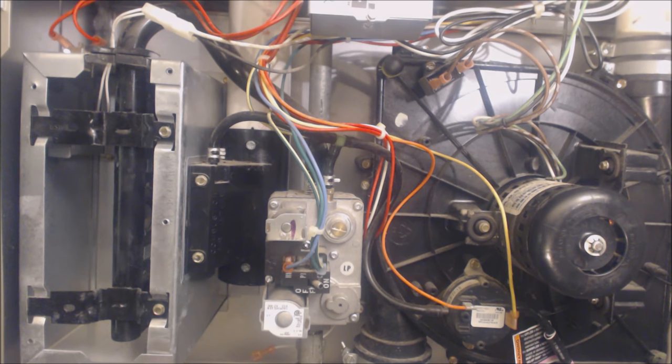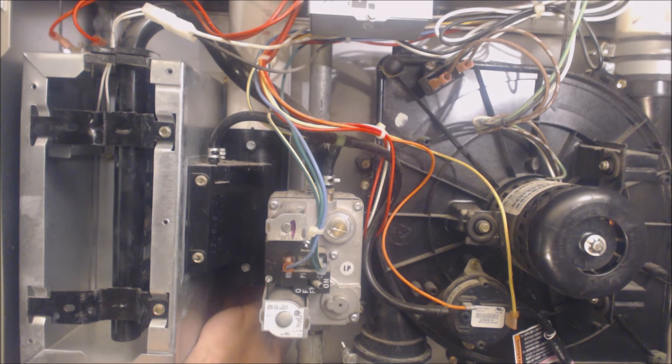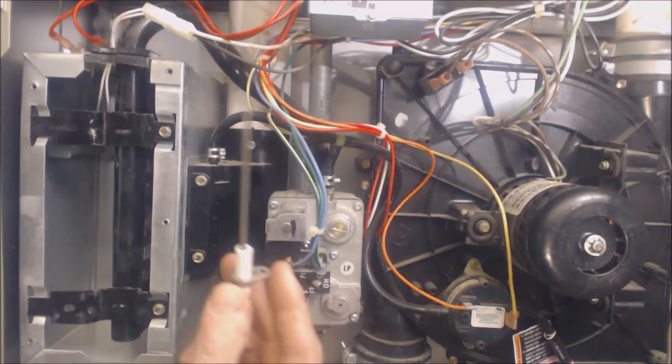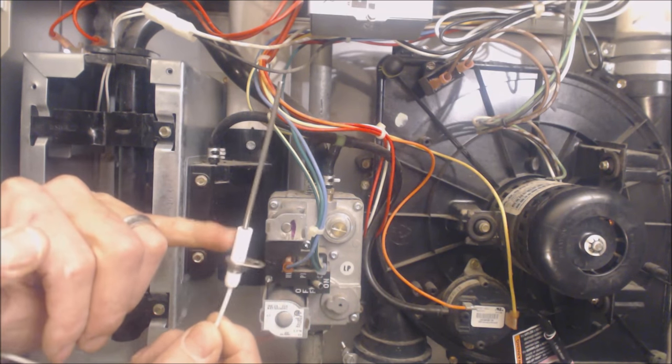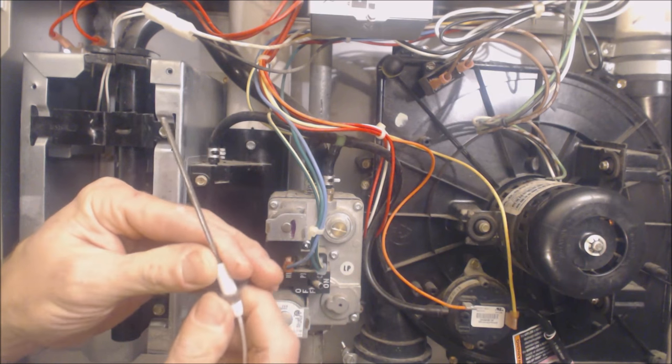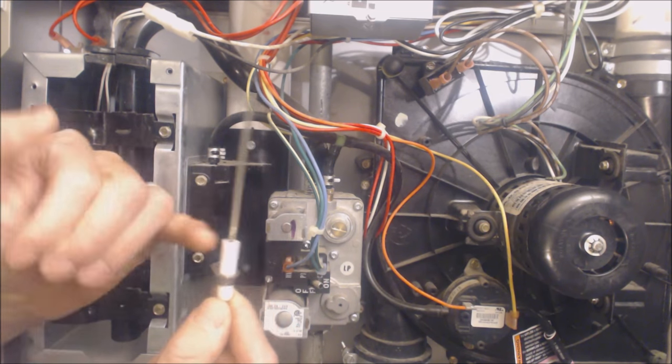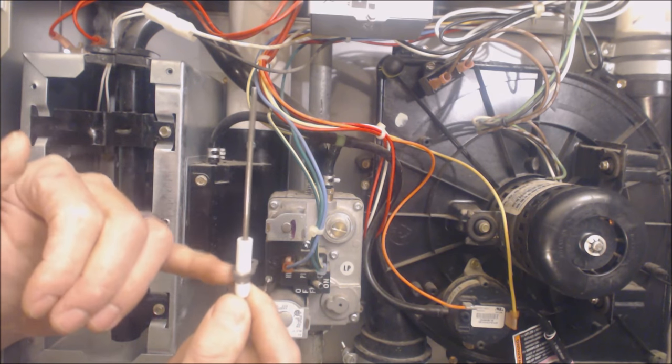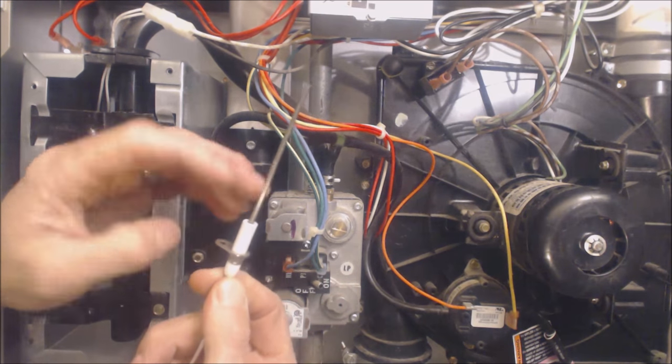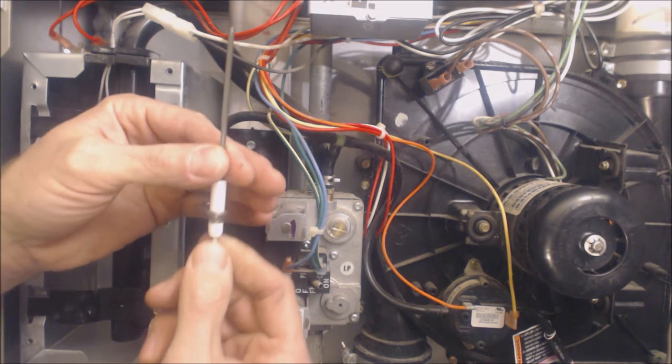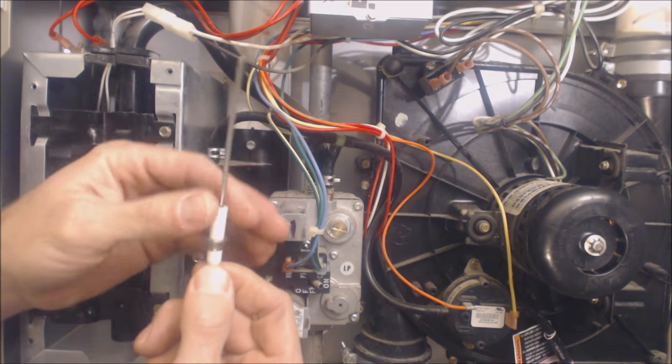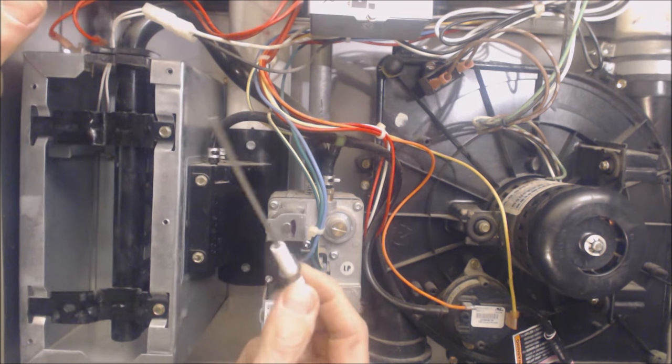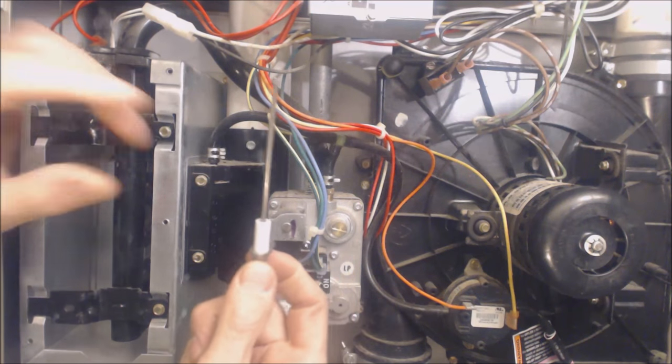Basically you have this wire right here. This wire attaches to a flame sensor rod. All this is is a stainless steel rod and this right here is porcelain and ceramic, and basically what it's doing is isolating the rod and the voltage that the control board or module is putting into the burner or flame area. It's isolating that from the ground because you want to put the AC voltage into the flame.